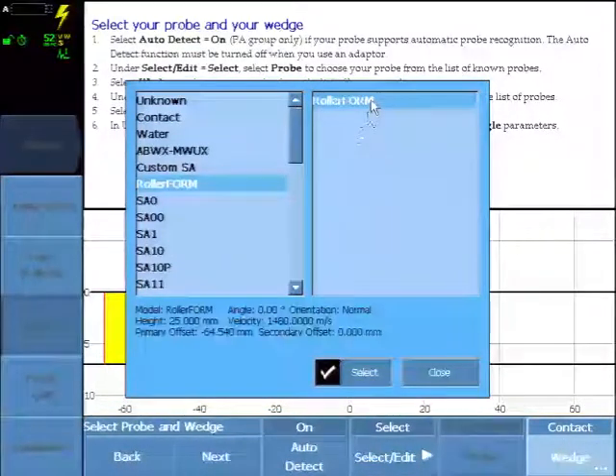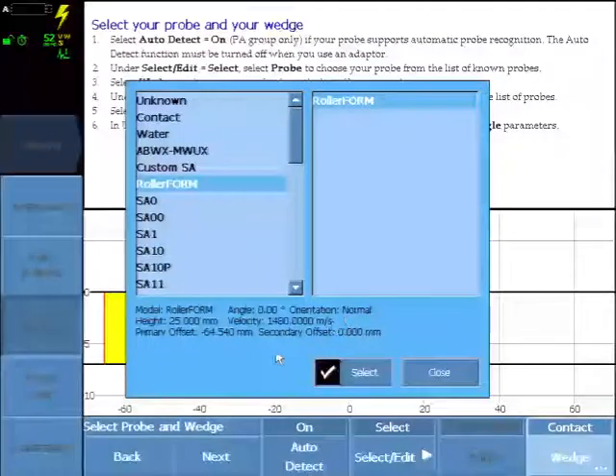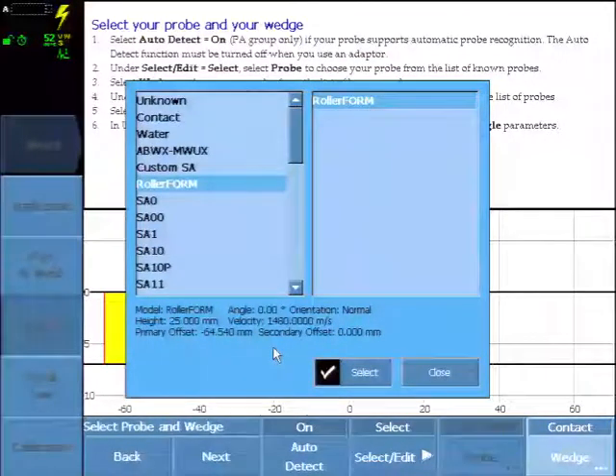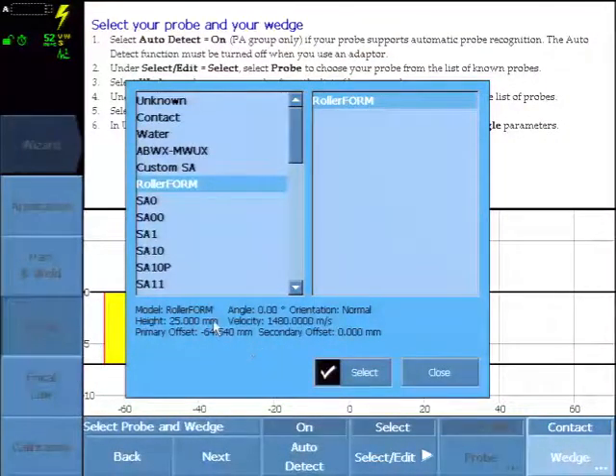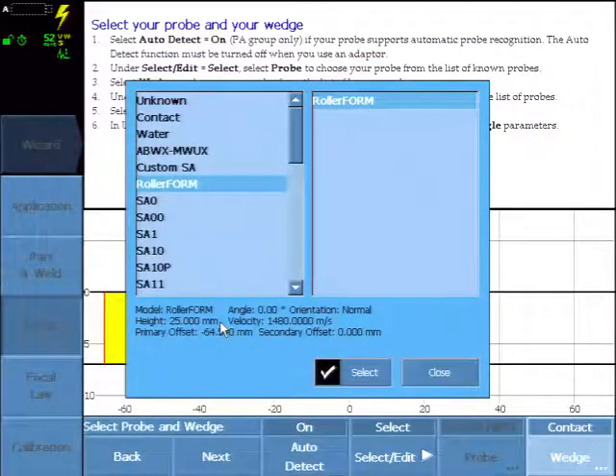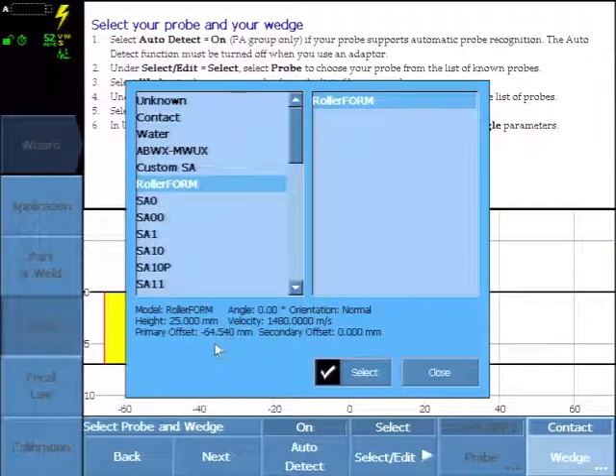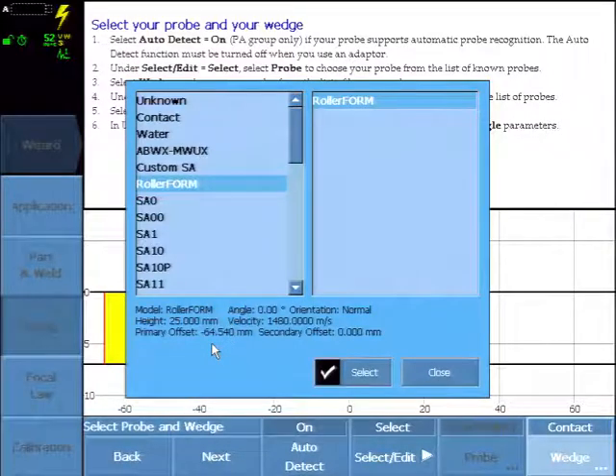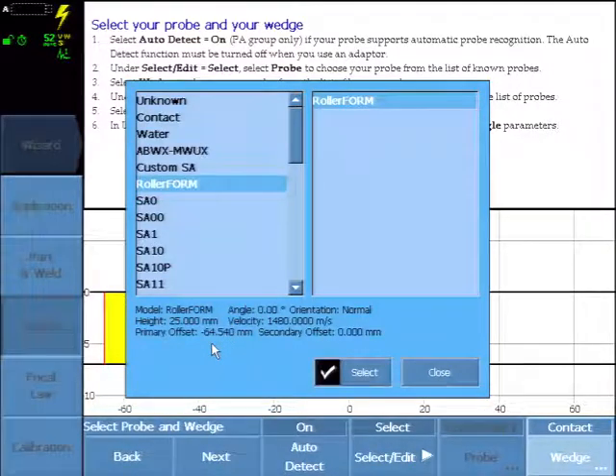Select the roller form from the database and this is a water wedge with a 25 mm standoff and the offset set for near wall inspection.